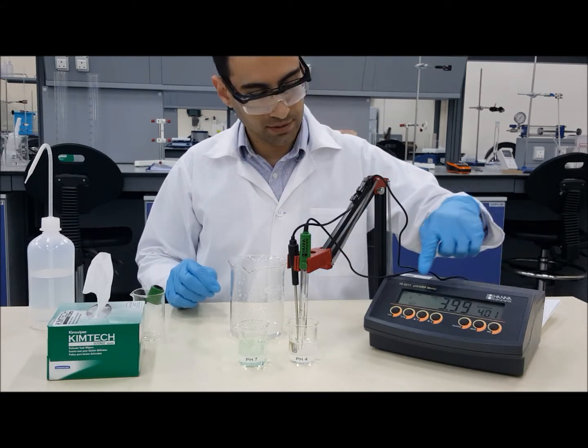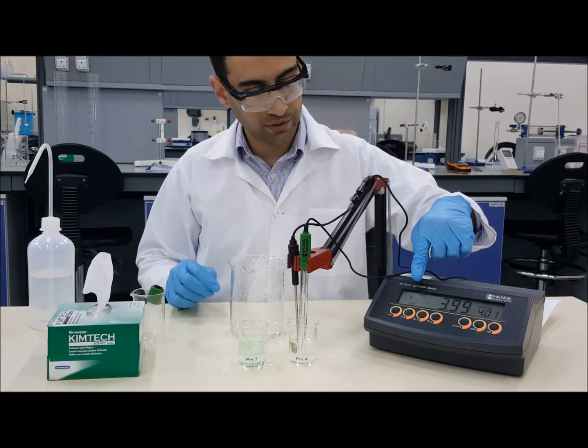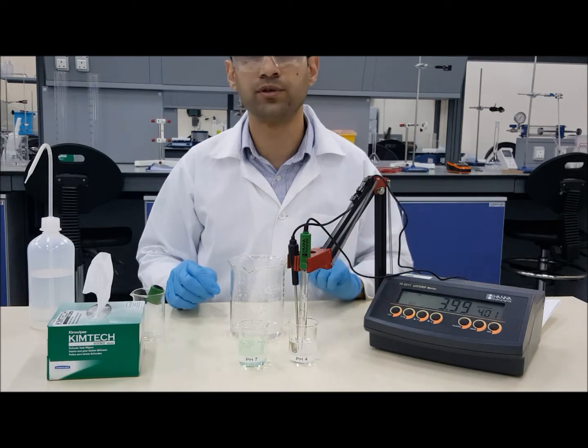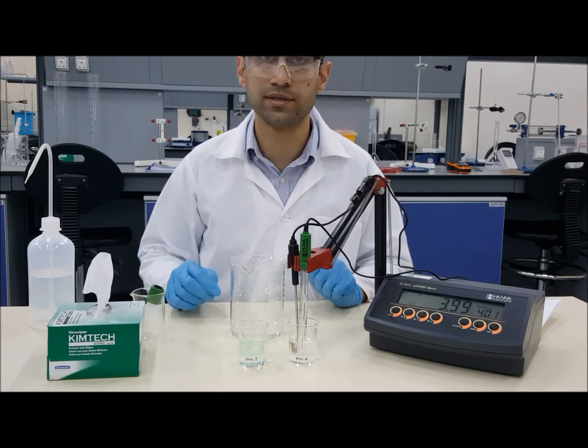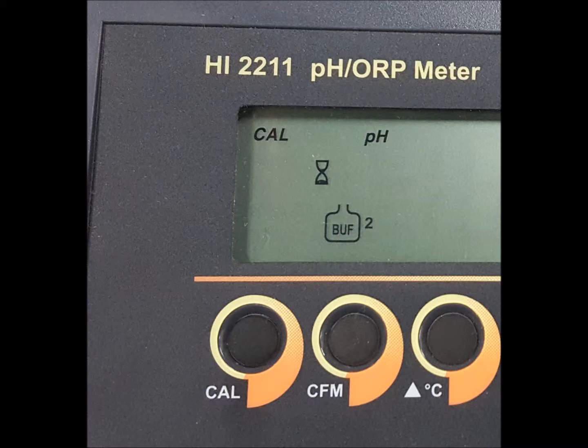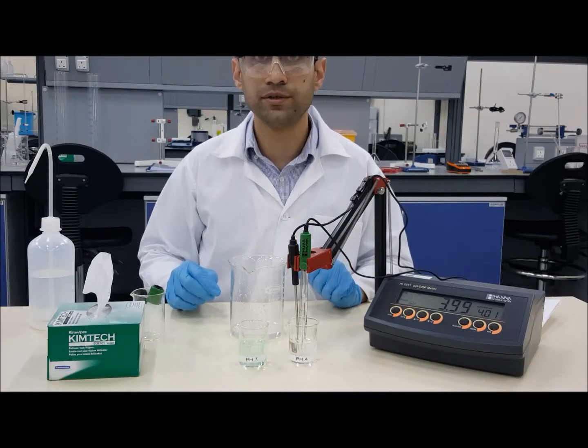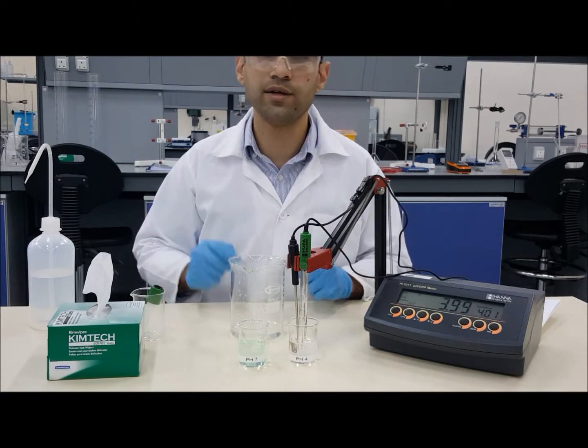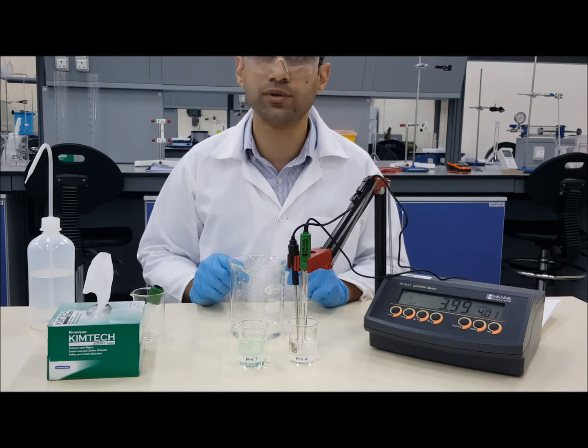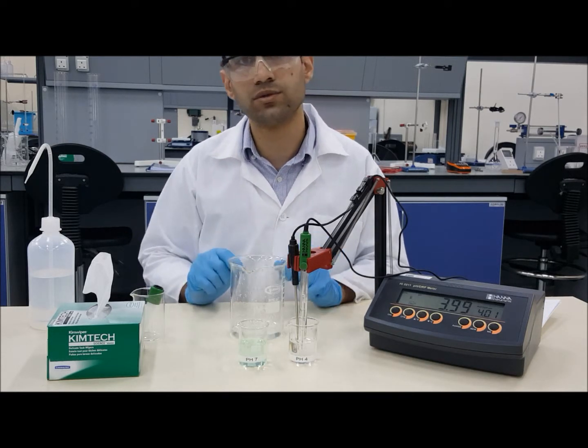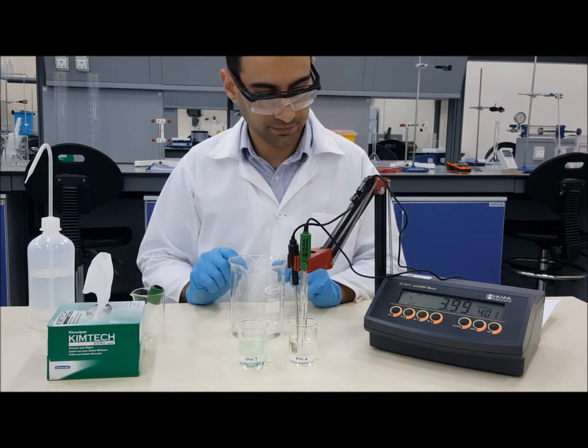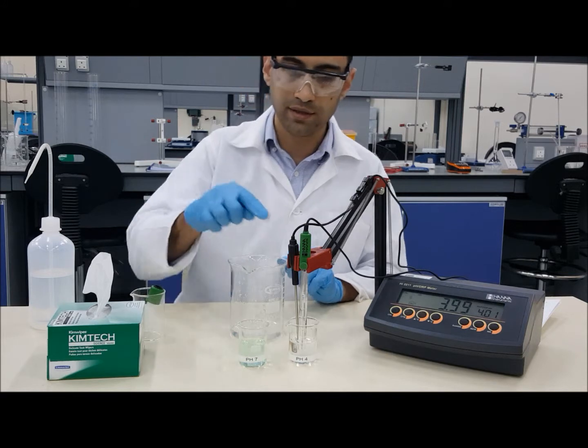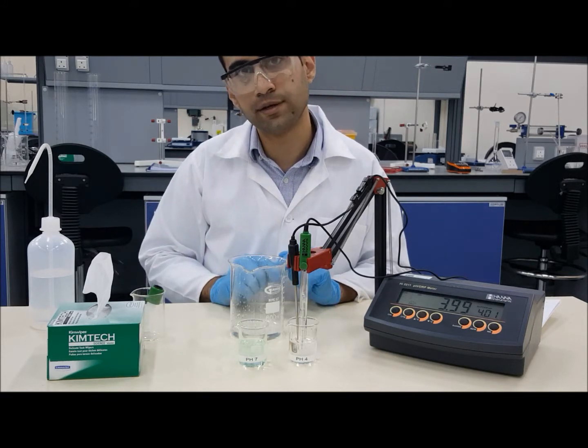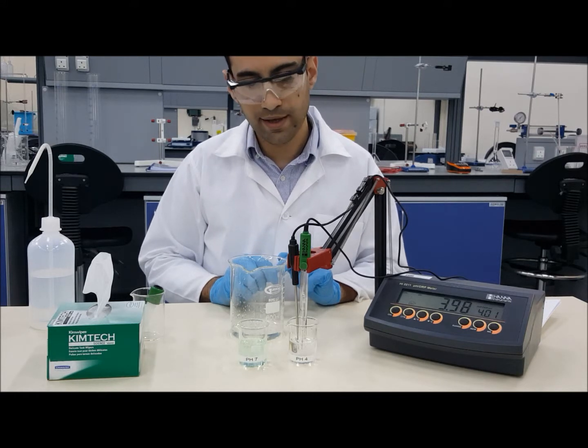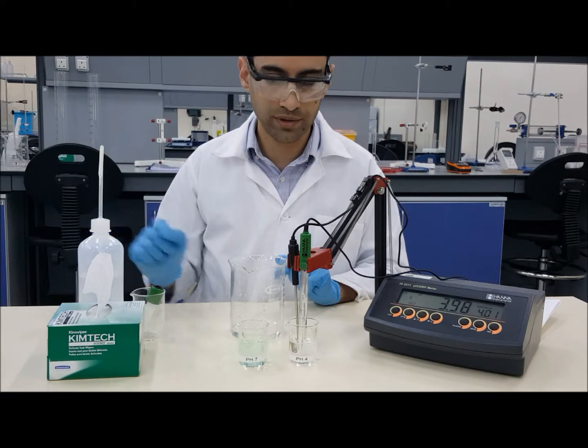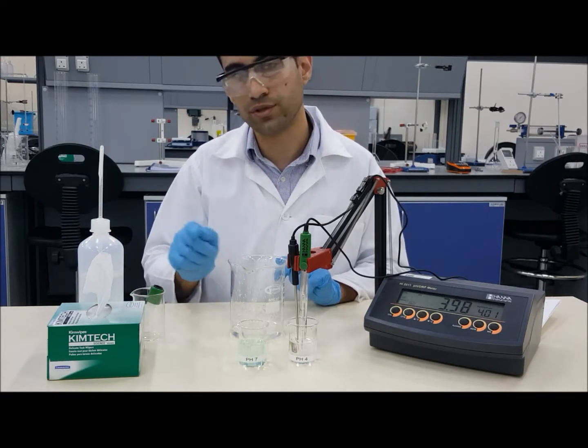In this buffer solution, we are going to see a small logo there showing buffer and a small number 2, which means this buffer solution is number 2. This is a 2-point calibration which has 2 buffer solutions. We can do also 1-point calibration, but in order to get more accurate values, it's always good to have the 2-point calibration. Always remember, while using the pH meter, the temperature probe should be with the electrode together in the solution you are measuring, and always use water to rinse both before changing between solutions.